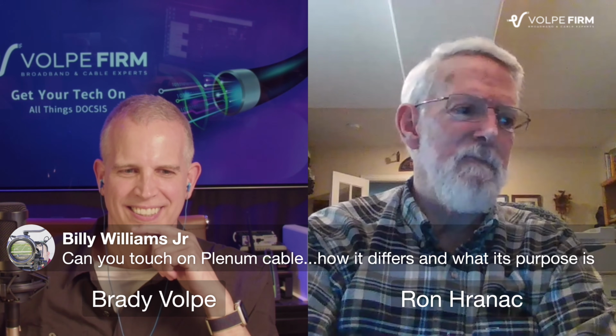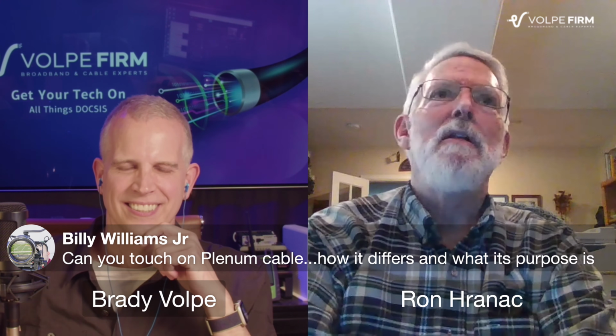They defined four categories, basically UL Underwriters Laboratory listings for drop cables, or cables in general used in premises - there was CATV, CATV-X, CATV-R for risers like elevator shafts, and then the plenum-rated cables. They all had to do with the release of smoke and the ability to propagate flame.